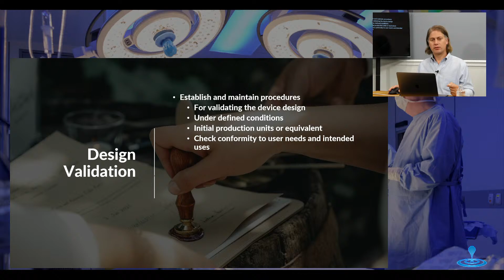Validation from the regulatory perspective isn't gathering data so that you can write a better paper. It's about showing that the user needs and intended uses of the device have been met. And sometimes that can be simpler than people think. Sometimes there are products that have only one user need. And the validation of those is very, very simple, and it's the use of a simulator by a trained user. Other times it can be more complex and involve clinical trials. But the reality is that validation isn't the same thing as academic research. It's something for a specific purpose to demonstrate conformity to user needs and intended uses.